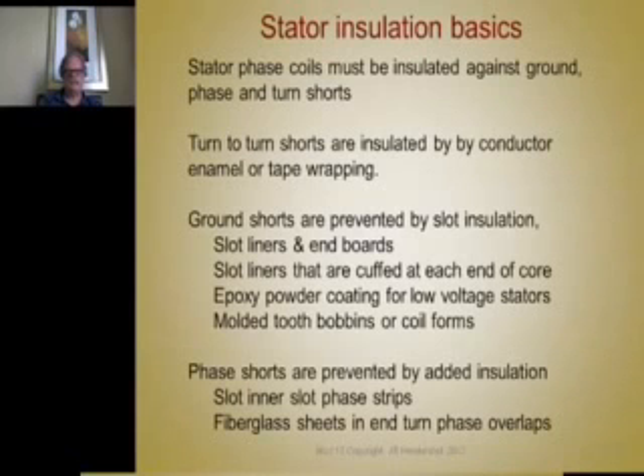Simple basic considerations for insulation systems. The stator phase winding must be insulated against ground shorts and turn-to-turn shorts. Turn-to-turn shorts are insulated by the enamel coating on the conductor, or at higher voltage, they are insulated by wrapping tape around the magnet wire. Ground shorts are prevented by the slot insulation, slot liners and end boards.